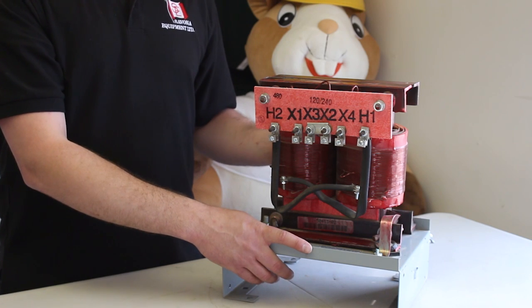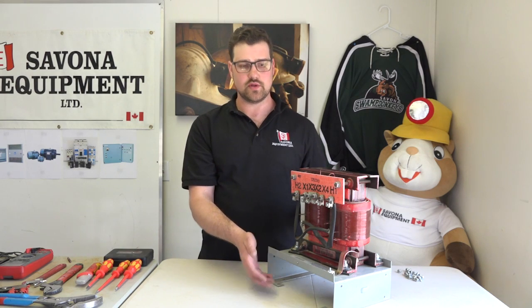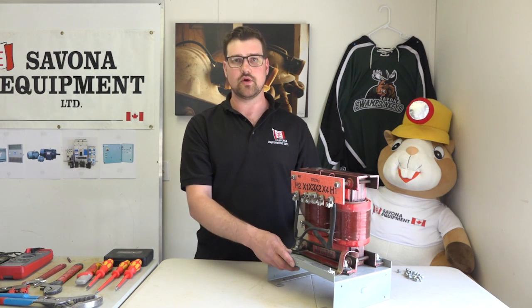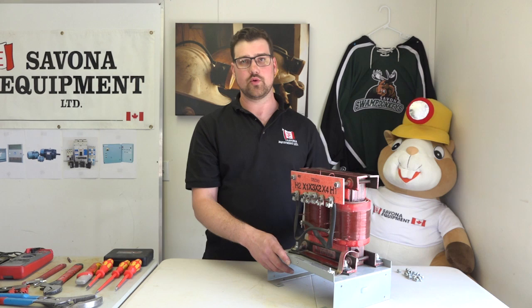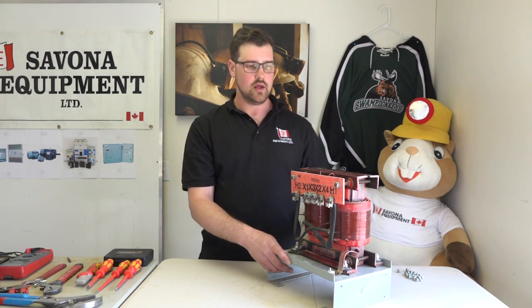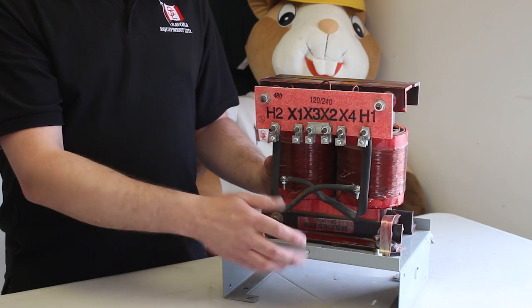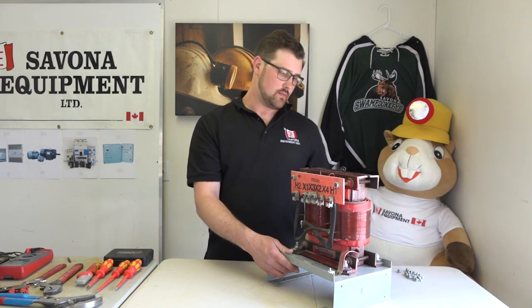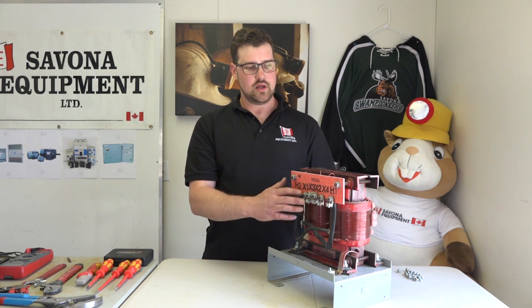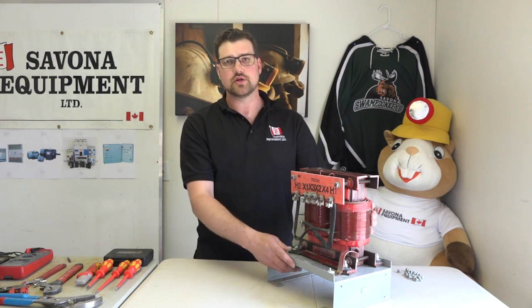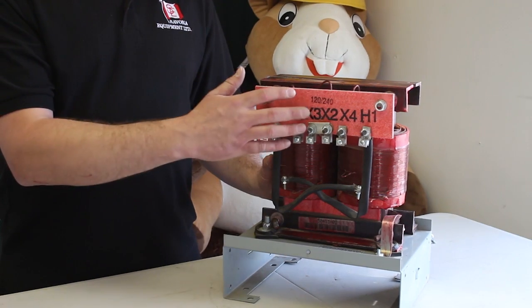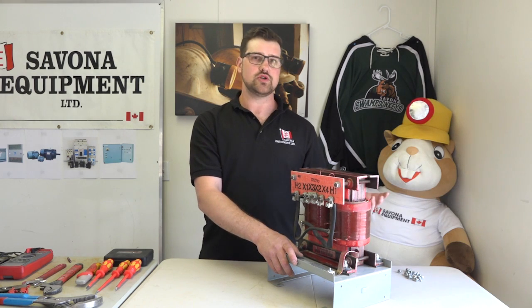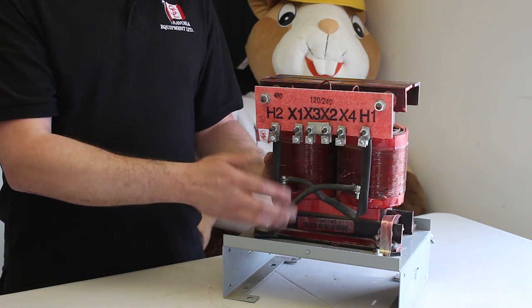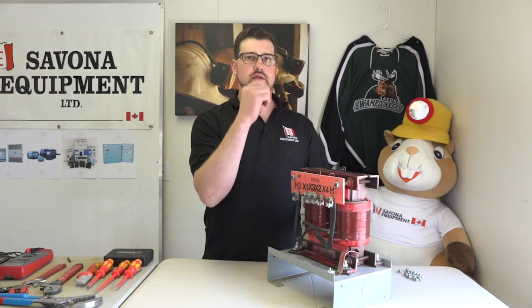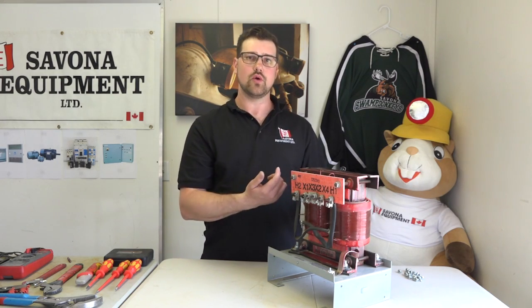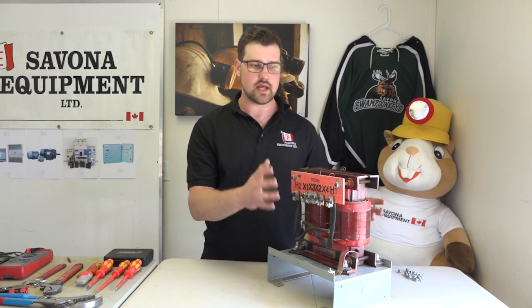Another little tidbit of information with transformers is that they come with ratios. This particular transformer, 480 to 120/240, would give you a basic ratio of 4 to 1, just 480 divided by 120. And then on the 240 side, 480 divided by 240, which is a 2 to 1 ratio. You can get into the 3-phase ones. You have, for example, 600 to 120 would be a 5 to 1 ratio, and then 600 to 208 would be a 2.88 to 1 ratio. That gives you an idea. It's the number of windings around the iron core, and just a basic understanding of how that works.